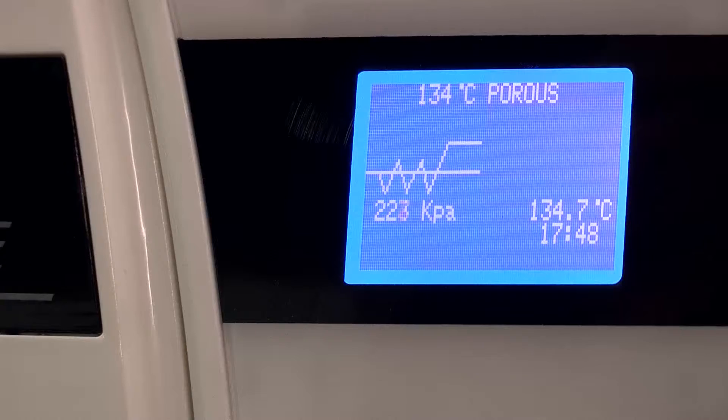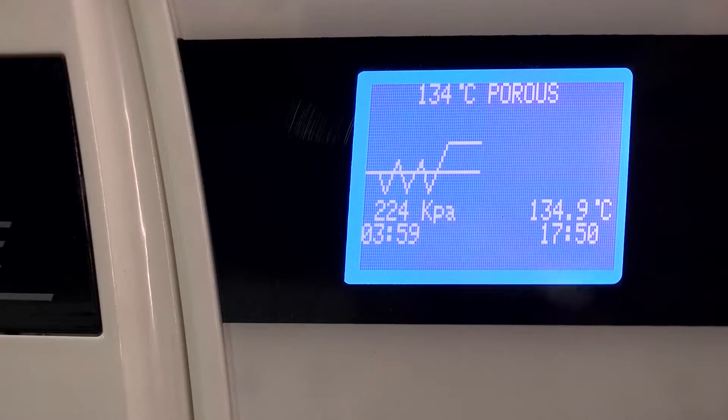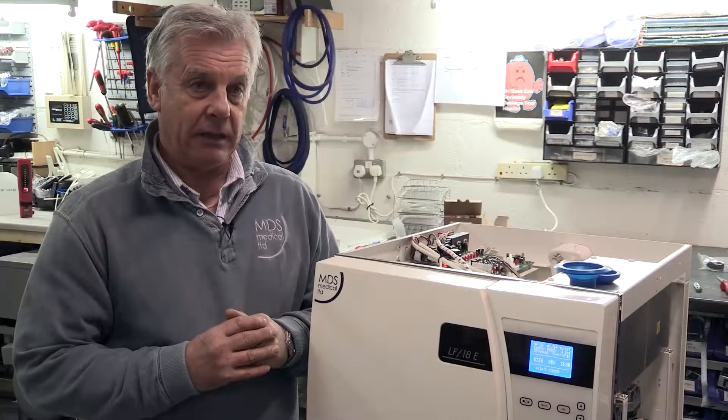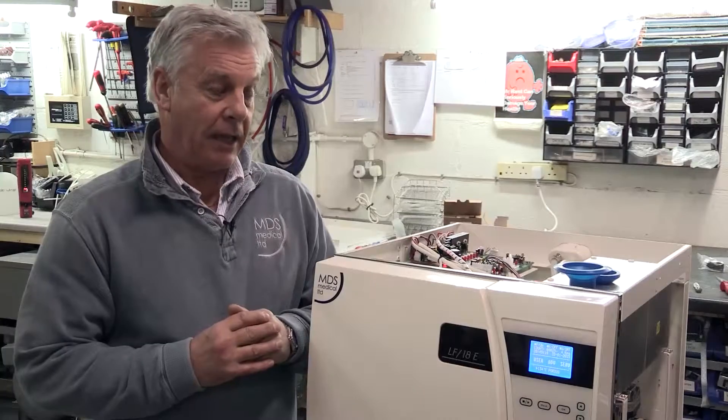If we can do that then we know that we can go on to the sterilizing stage of 134 degrees C for three to four minutes. That will kill any bacteria that are known to man at those temperatures.